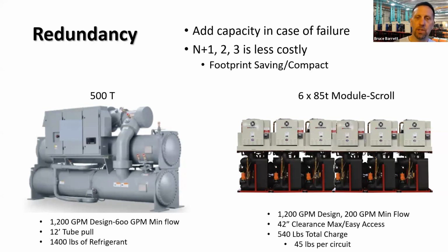Clearances. A shell and tube machine can have a very, very large footprint, not only side to side, but above. Modular chillers are very short, compact. We can move them around corners, move them around poles. Structural components, that can be easily done by just providing a spool piece to span that gap around a pole. So we've done a lot of those where there's installation challenges based on the mechanical room. Getting a module, say it's up to the penthouse or into the basement, these can be put on a freight elevator. Regular elevators typically will meet the weight requirement. Put them on a hand cart, pallet jack them around the building, stack them, connect them victaulically together, and you've got a 500-ton chiller built.